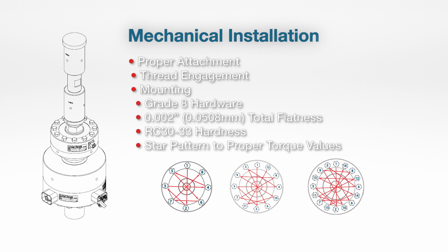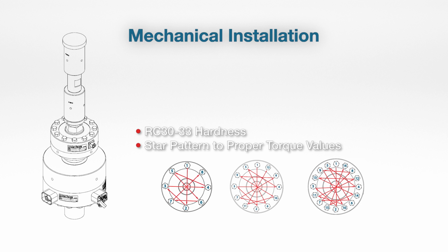Now, the load cell you see there is actually bolted up to a base. If you can see my cursor here, we've got another picture shown specifically, but that's the lower half of the load cell. Always recommend using high-quality hardware, grade 8 or better, when you install it either to a base or to your own mounting plate. We recommend that whatever you mount it to is 2 1,000ths total flatness, and our bases are typically RC30 to 33 on the hardness scale. When you are installing it, we recommend following a star pattern just like you would torque a wheel on a car.